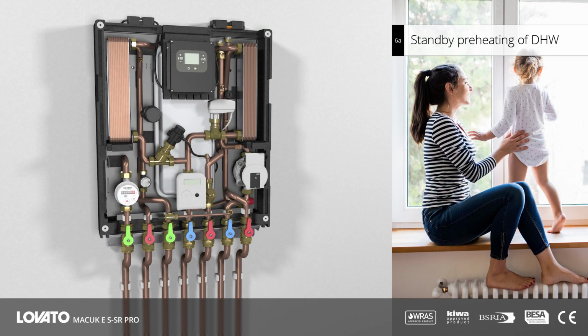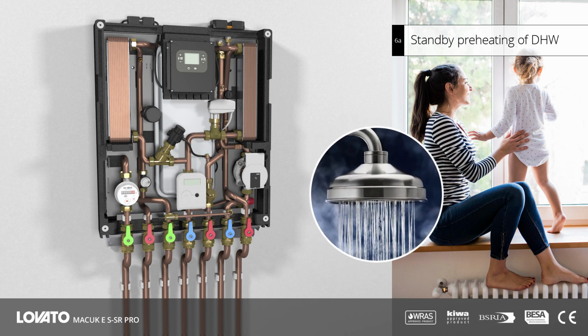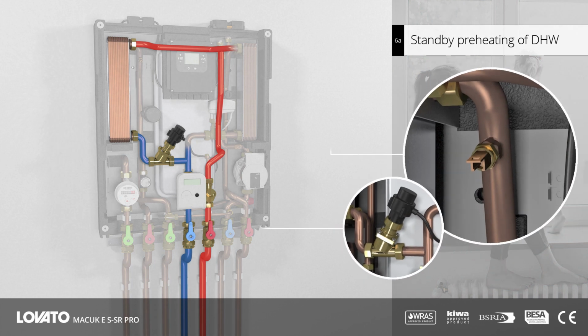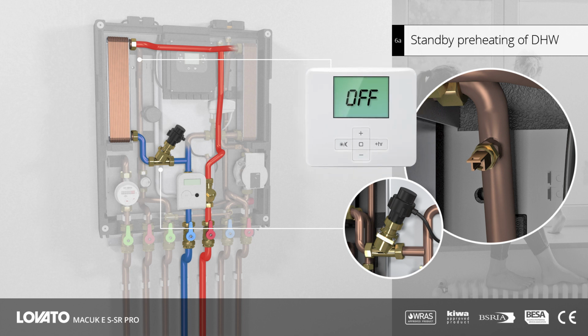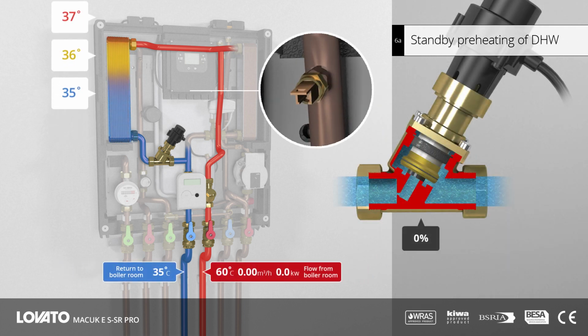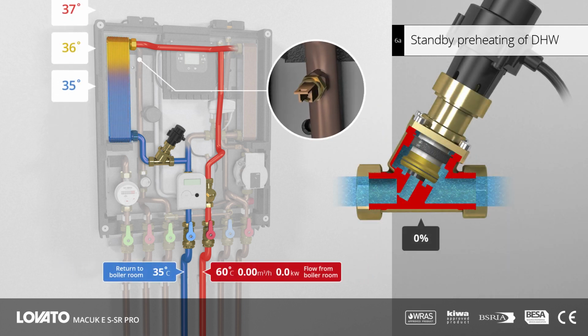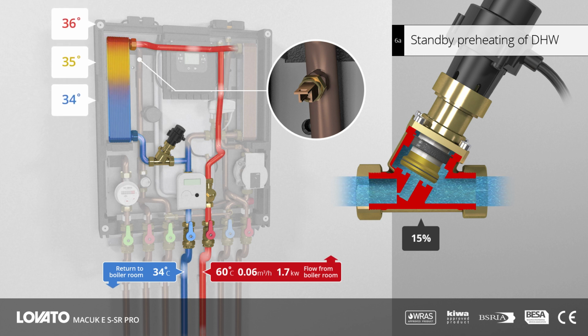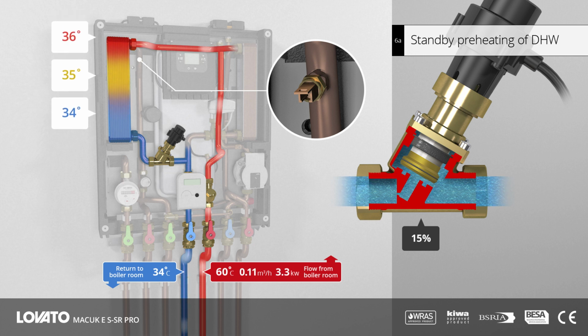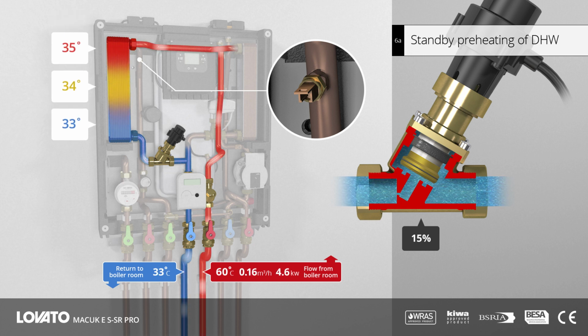The Macuk E is electronically controlled for maximum comfort and efficiency. To ensure instant demand for domestic hot water, an electronically controlled hot water bypass provides a route for flow under minimum load conditions. When all radiator control valves are closed and there is no demand for hot water, the stepper motor reacts to a temperature sensor upstream of the heat exchanger and the valve opens just enough to allow minimal flow. With this balanced control and hot water continually present in the primary feed, domestic hot water of the desired temperature is always instantly available.